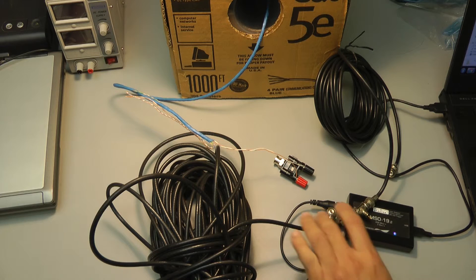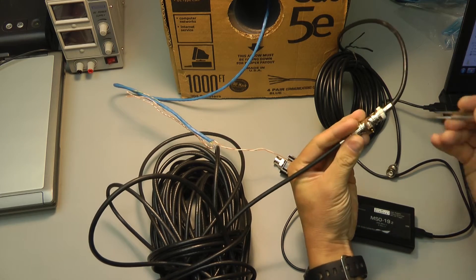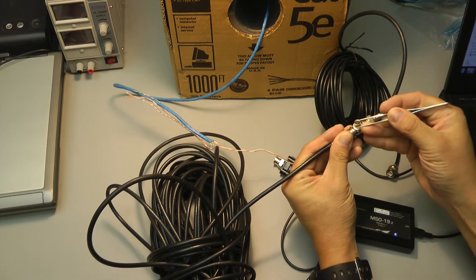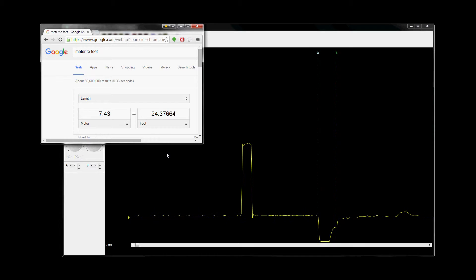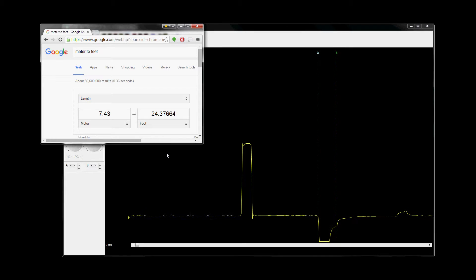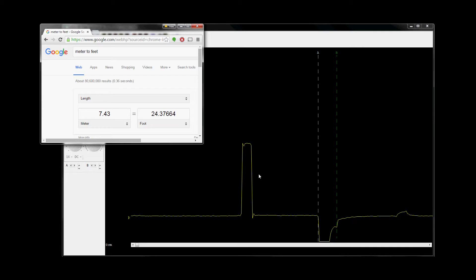Now this is something interesting. I left this connector open — what happens if you have a short in the cable somewhere in the middle of the cable chain? You can see the short is exactly at 100 feet. You see the inflection going down, and then it starts climbing back because part of the energy that didn't get absorbed started reflecting back at the end of the 25 feet. One pulse goes at 100 feet, it sees the short, goes down, and then starts climbing back up. This tells me the length of the second section, and here's the mismatch.